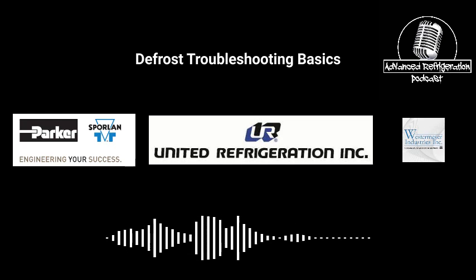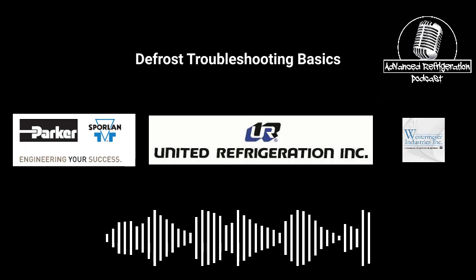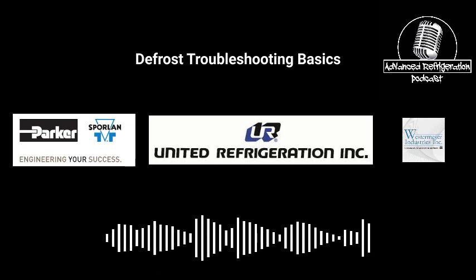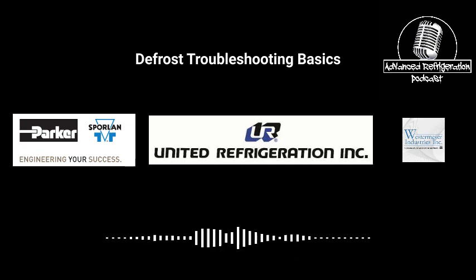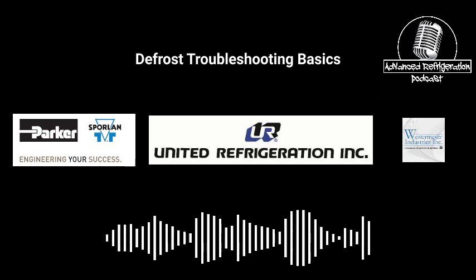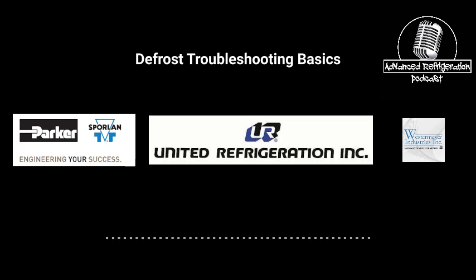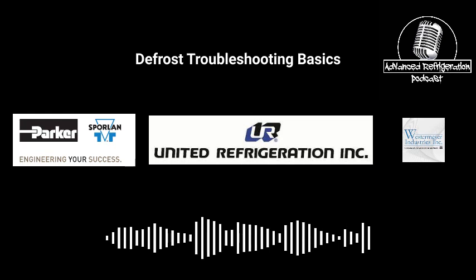Honestly, it's an easy upsell. Some customers are hesitant about it, but what's it cost to de-ice 3 freezer coils with the whole ends? It's got to be an easy $800-900 service call. And if you're doing that 3-4 times a year, every time you do a PM because they're iced up, because they all build ice, they don't get hot enough because there's not enough heater on the ends of the coils, because all these manufacturers keep shrinking that heater down to save a little bit of money. Or the heater walks more toward the electrical side; those heaters move back and forth. So having that dedicated heater on the TXV side solves all those problems.